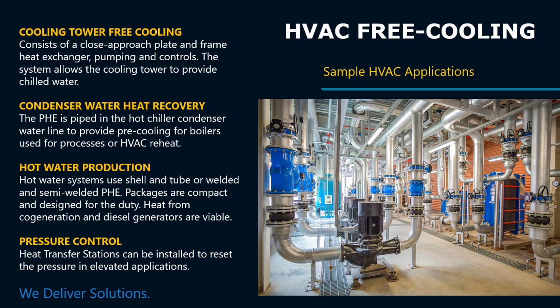Another option is the condenser water heat recovery. The plate heat exchanger is piped in the hot chiller condenser water line to provide free pre-cooling for boilers used in processes or for HVAC reheat systems.